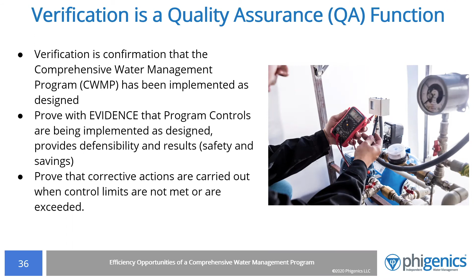Here's another example. There are various ways to verify your program. You can check operator logs, flushing logs, and other records. A water management team set a target of maintaining 0.5 ppm of free chlorine at a distal location in their cold water system in order to maintain hazard control throughout the entire water system. The manpower required to take the readings was significant, so they installed a chlorine analyzer that took readings every couple of minutes. The chart you see is averaging the daily numbers.